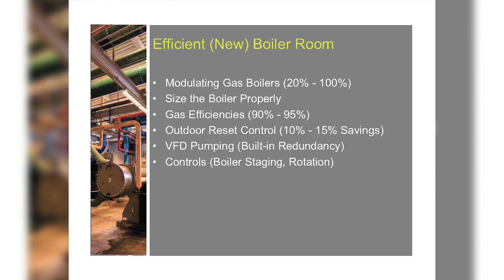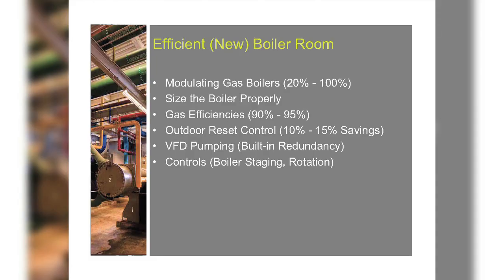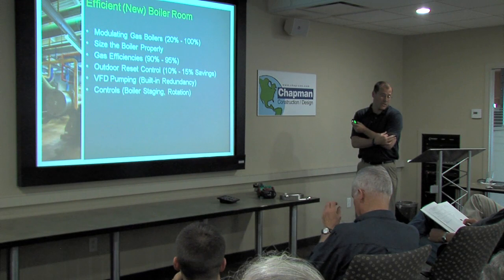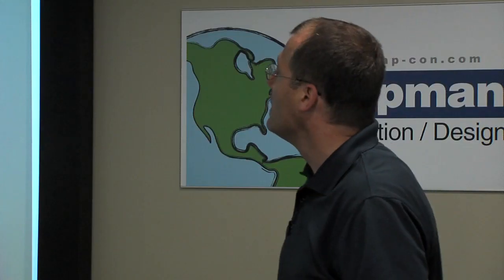Today, what's changed is our burners are no longer single speed or one stage, they're modulating. And coupled with outdoor reset or weather responsive control, if we can watch the weather and say, on a 50-degree day, the building only needs 120 degrees of water instead of 180 degrees of water, then let's slow the burner down. So we use that outdoor weather responsive control to modulate the burner. Several ways it's done, but typically you speed up and slow down the fan that brings fuel in, and that's how you speed up and slow down the burner's firing rate. So if we can lower water temperature, for every 3 degrees of water temperature we can reduce for heating the building, it's about a 1% efficiency gain. So most of the year we're above 30 degrees. So there's a huge opportunity with just changing the boiler to something that modulates to gain huge savings.